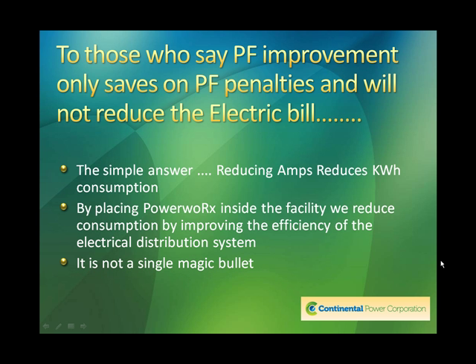To restate it another way, for those who say power factor improvement only saves on power factor penalties and will not reduce the electric bill, the simple answer: reducing amps reduces kilowatt hour consumption. Let me state that again. Reducing amps reduces kilowatt hour consumption. By placing PowerwoRx inside the facility, we reduce consumption by improving the efficiency of the electrical distribution system. And that's key. Underline in your mind the word efficiency. We improve the efficiency of the electrical distribution system. And it's not a single magic bullet. It's a whole series of small savings.